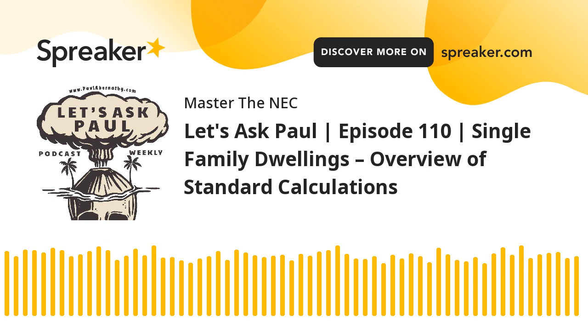And then you add them all up like you did before, divided by the 240, which is your system voltage, and that's going to give you a minimum ampacity. And so when you've got the minimum ampacity, at that point, you've got to size the neutral. Now, a lot of times when it comes to the neutrals, people get lost in this because, again, you've got to size a neutral to handle the maximum imbalance load, and that's basically what you've done. You've just done the calculation, okay?